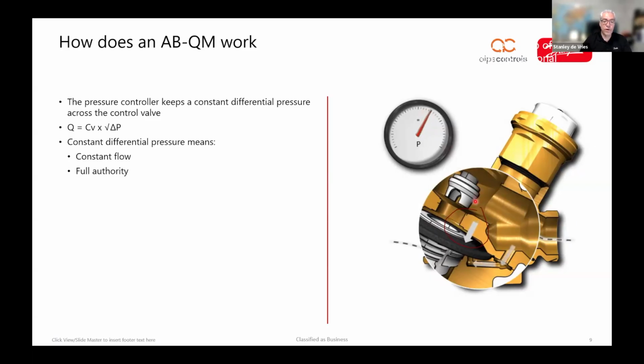We know exactly what the flow is when the valve is fully open. We know what the flow is when the valve is half closed. And that means we also have full authority on the valve, which is a bit different discussion that I don't have time to go into today. But this is the basic idea behind a pressure independent control valve. By keeping the pressure controlling function separate from the control valve, we can let the control valve do its work the way it was intended.